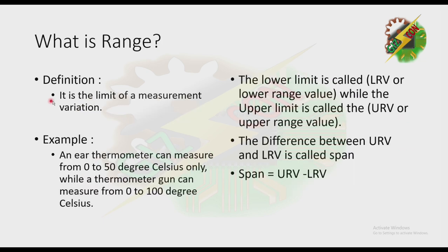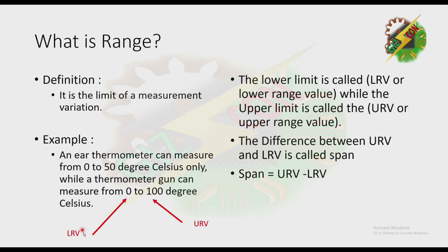What is range? By definition, it is the limit of measurement variation. For example, an ear thermometer can measure from 0 to 50 degrees Celsius only, while another thermometer can measure from 0 to 100 degrees Celsius. The lower limit is called LRV or lower range value, while the upper limit is called URV or upper range value. 0 here is the LRV and 100 here is the URV. The difference between URV and LRV is called SPAN — SPAN is equivalent to URV minus LRV.